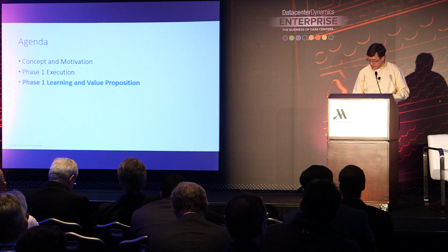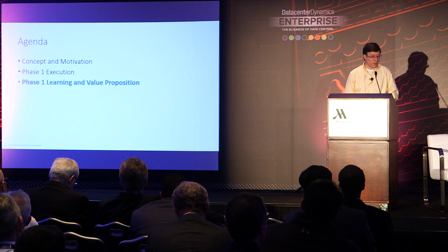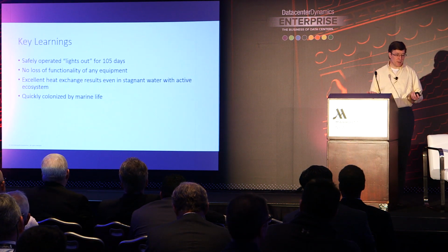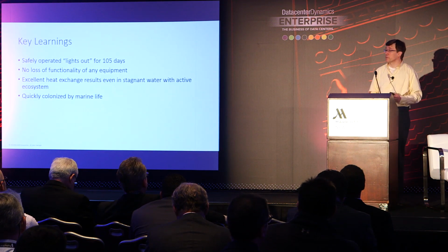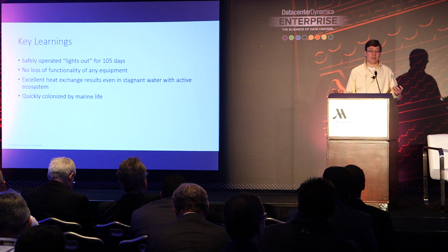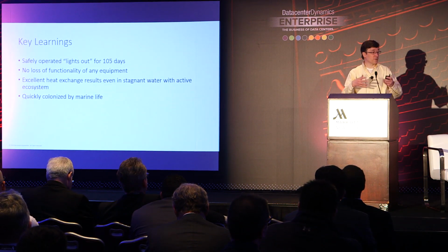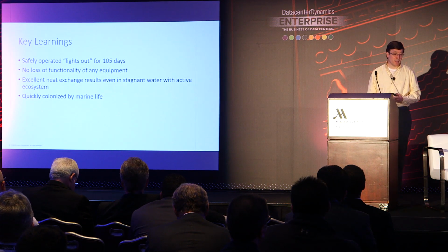So we did all that, and we pulled this out of the water last fall, and what did we learn from all of that? Well, I think the first thing is we had planned to go in for a month, and after a month everything was fine. So we decided, well, let's just keep going, and we'll see what breaks first. Ultimately we were in the water for about 3.5 months, and eventually pulled it out because everything was still fine. So it's not statistically significant. It's a very small number of servers, but obviously if we had been flooded or if things had started to fail in some strange way, that would have been indicative. So we were quite happy with that.